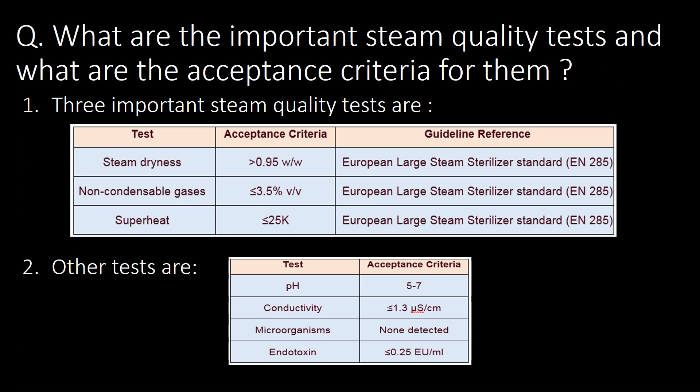What are the important steam quality tests and what are the acceptance criteria for them? Steam dryness, non-condensable gases, and superheat are the three important steam quality tests. You can refer to the table below for acceptance criteria as per the European large steam sterilizer standard, EN 285. Other important tests are pH conductivity, microorganism content, and endotoxin.